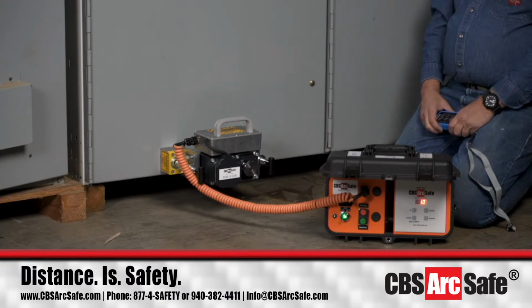So we've worked to test a lot of circuit breakers in our Gainesville warehouse of our sister company, Circuit Breaker Sales, so that we could know what type of force it would take to rack the breaker in and rack the breaker out.